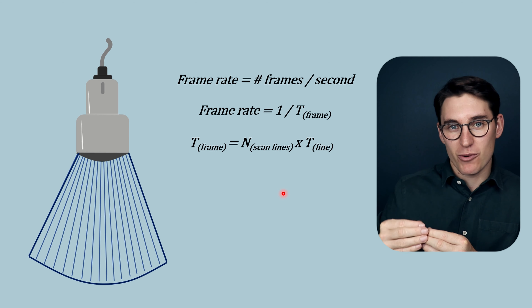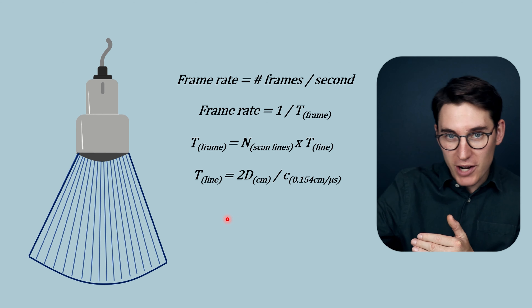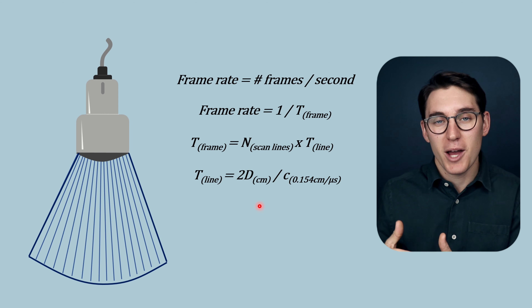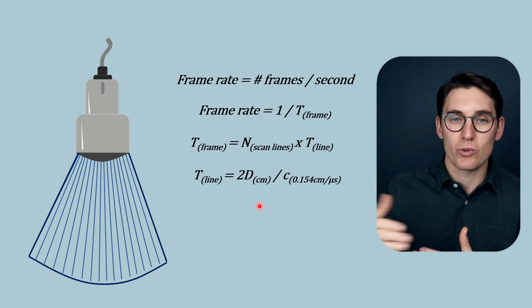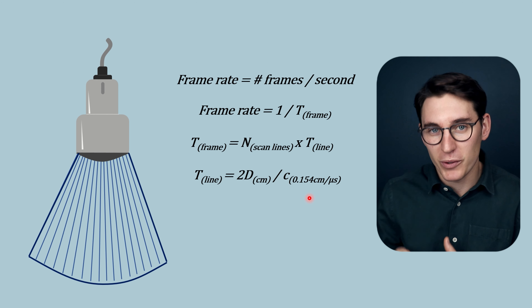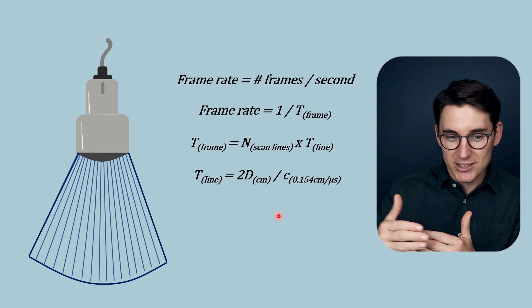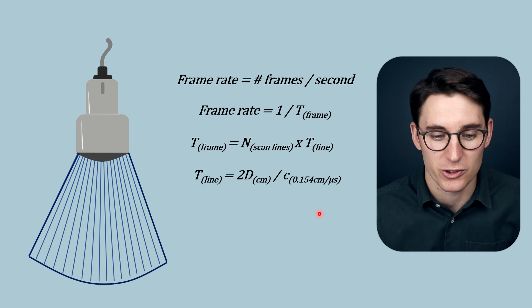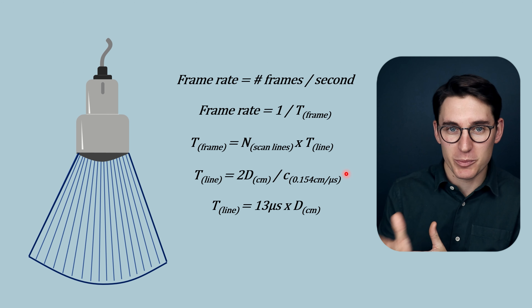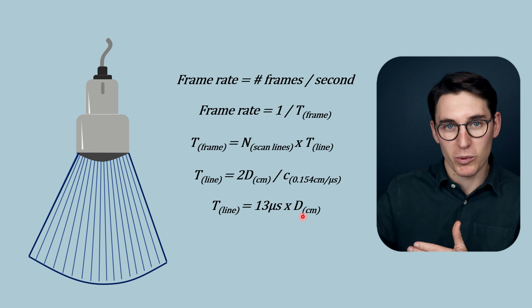We can calculate that round trip time by taking the depth we want to image and multiplying it by two — we travel the depth into tissue and the same distance back. We then divide that total distance by the speed of sound in tissue, which gives us the total round trip time. The speed of sound in soft tissue is 1,540 meters per second. Converting to centimeters per microsecond, the time it takes for one line of data to be acquired is 13 microseconds times the depth we want to image. Increasing depth increases the time to acquire a single A-line.